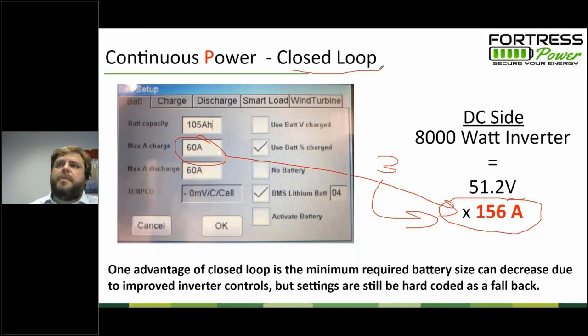Here we have an example of closed loop where, for this particular inverter manufacturer, they have a BMS setting, and our BMS in their system is number 4. When we use their BMS setting number 4, it knows that I'm using the inverter with these batteries, and that allows us to say: normally with open loop, we need 3 of these batteries, but since it's using closed loop communication, we can do 2 of these batteries.